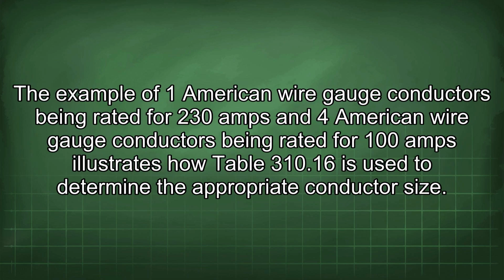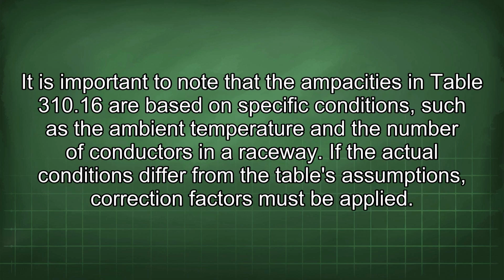The example of 1 American wire gauge conductors being rated for 230 amps and 4 American wire gauge conductors being rated for 100 amps illustrates how table 310.16 is used to determine the appropriate conductor size. It is important to note that the ampacities in table 310.16 are based on specific conditions, such as the ambient temperature and the number of conductors in a raceway. If the actual conditions differ from the table's assumptions, correction factors must be applied.